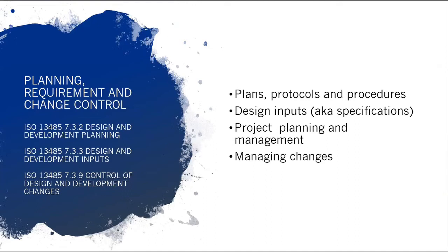So we'll get into some of the detail here, and these are linked to the specific sections of 13485 that refer to them. These are steps in the process, so you'll notice they're slightly out of sequence. The control and development of changes is brought in primarily to refer to the product once it's on the market and how to track it. But it's really important to trace changes that occur during the design process. So I've brought it to a higher level of consciousness earlier in the thought process.